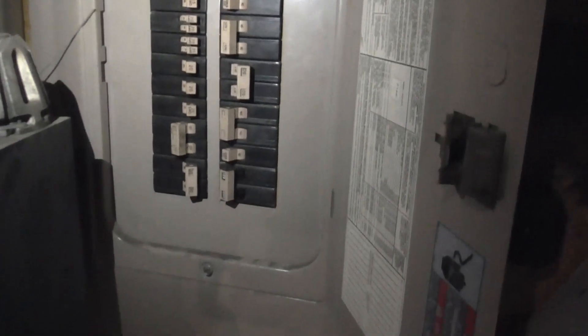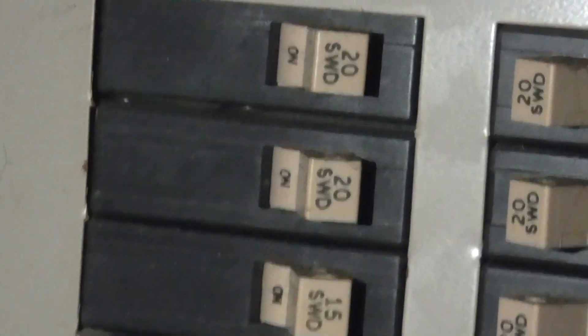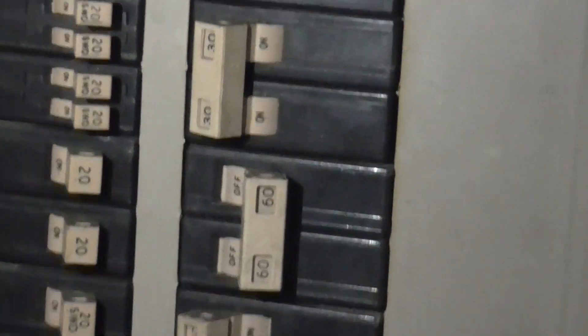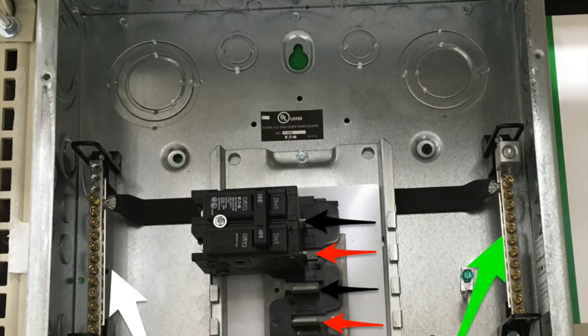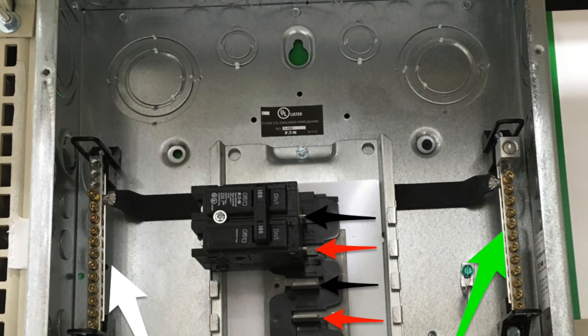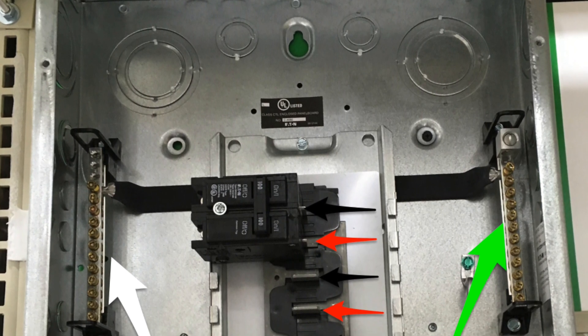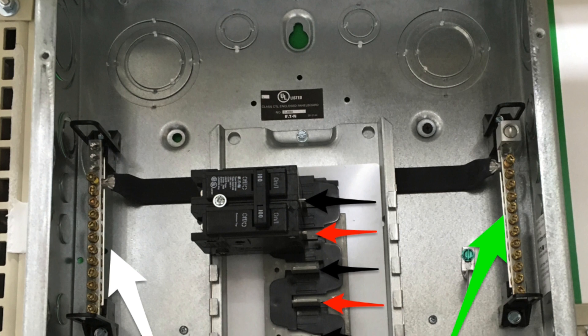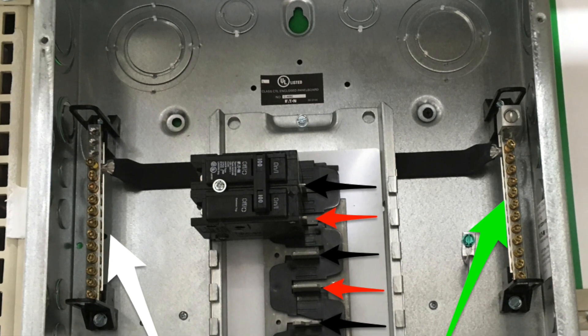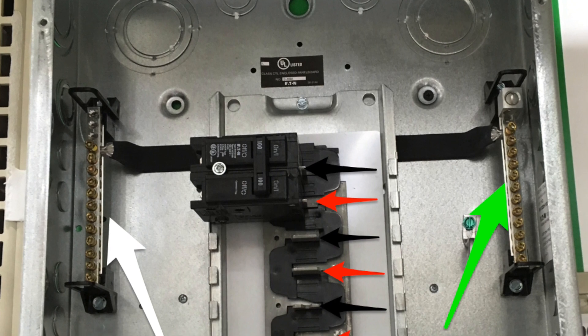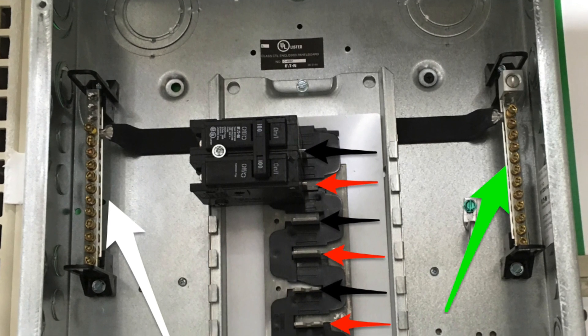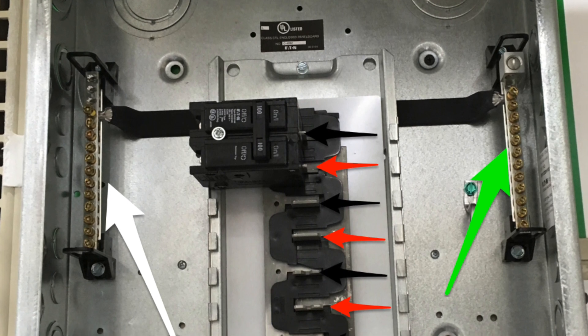So the wires come in, there's a main breaker in the panel. This one here is on the bottom corner there, and this breaker controls all these other breakers here. And each individual one of those is for 110 volt circuits. This one is a double breaker which is for 220, it's a common trip breaker. The way how this works is the two black lines that come in outside, one goes here one goes there. Then the line that's all bare exposed outside is the white one in here, the common, and then there's a green one which is the ground. And they have the bus bars. The green one's attached to a ground rod in the building.